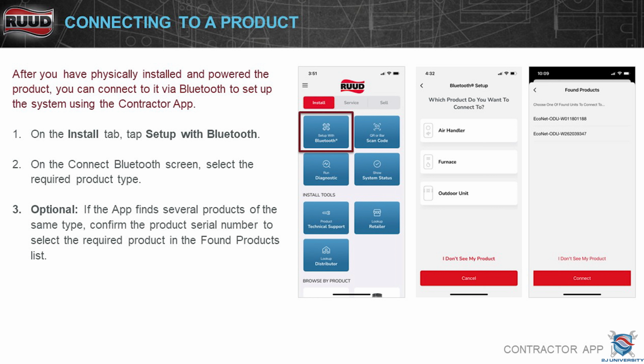You're going to click on Setup with Bluetooth through the install. You have air handler, furnace, outdoor unit. You click on whichever piece that you want, and it will literally walk through step by step exactly how to set that piece up. If you have multiple pieces that are connecting to Bluetooth, you're going to set up each individual piece. Okay? If you have multiple furnaces in the same space, you have to set both furnaces up individually. So it'll actually ask you which unit you want to connect to, and it'll show anything that's connected via Bluetooth. So if you have multiple furnaces or multiple air handlers, you'll have to select by serial number which one you want to connect to.